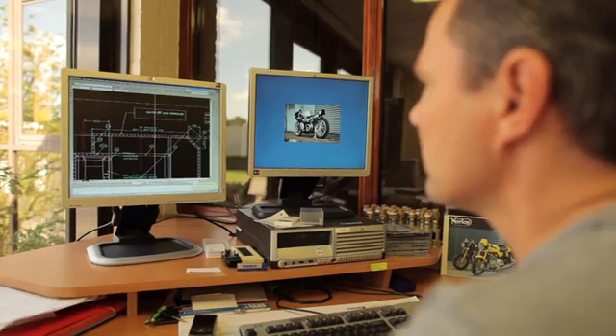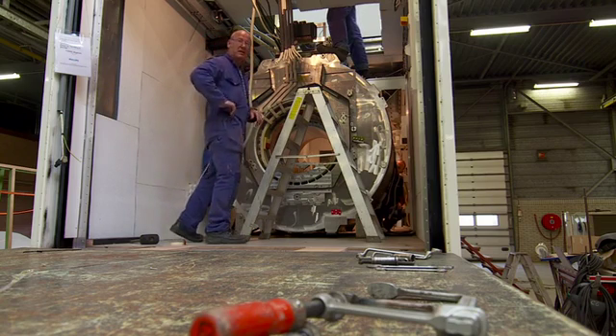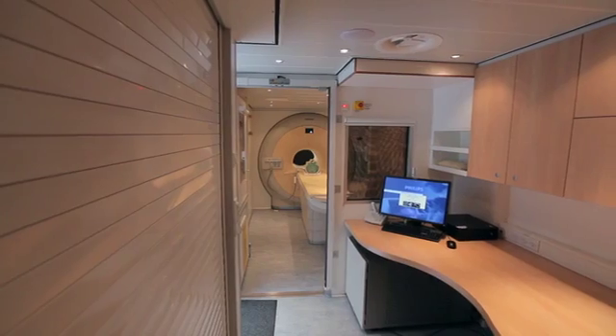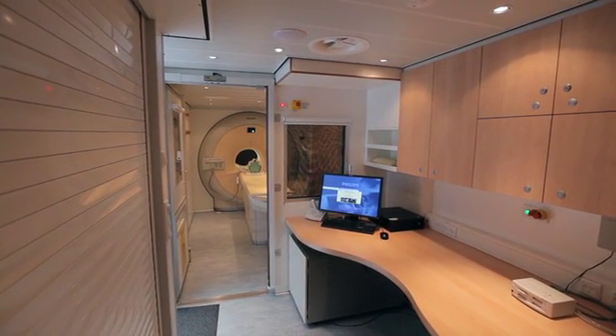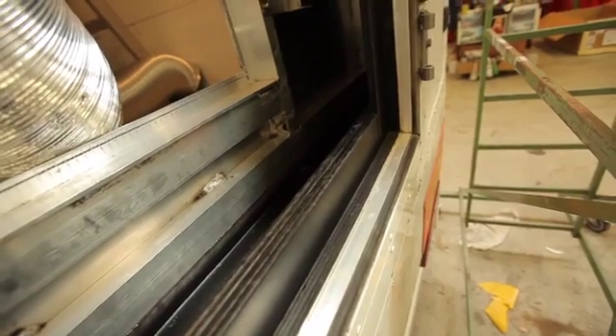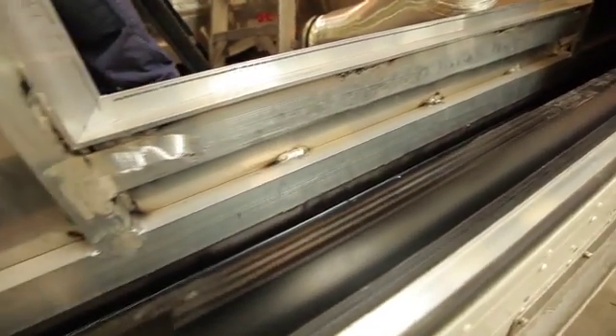Every unit is designed again for the purpose of the equipment being installed. The units we see here are mobile MRI units. For a mobile MRI unit we have to make sure that the system will be supported at all times. The running gear you will see — the complete chassis is made of aluminum, because a steel chassis, which is more or less used for commercial vehicles, would have too much influence on the magnet being installed later on.